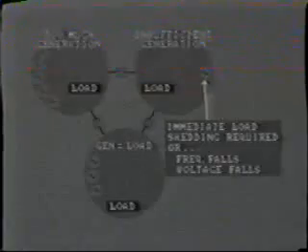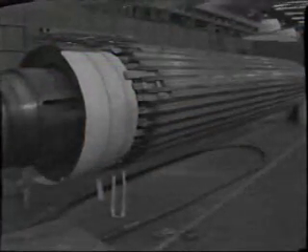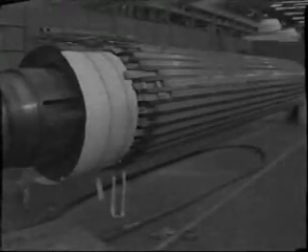In some areas, we will have too much generation available, hence the frequency will rise initially. In other areas, there will be insufficient generation, and if load shedding is not rapidly initiated, the generator will become overloaded. The consequence will be a fall in frequency, a fall in voltage, and a rise in stator current. The voltage regulator will increase excitation on the generator in order to maintain line voltage, and this may lead to overheating in the rotor. To protect the rotor, overcurrent protection is sometimes installed in the excitation circuit, and the relay set to alarm the operator.